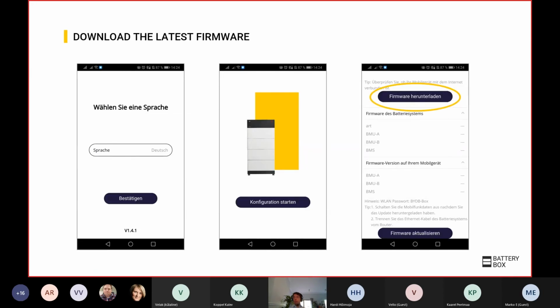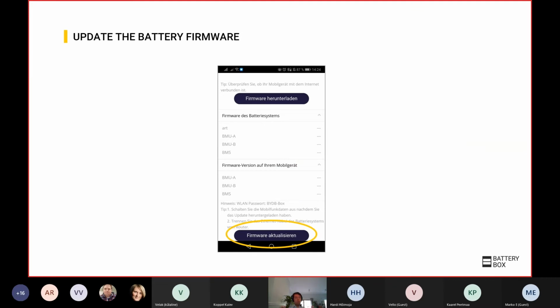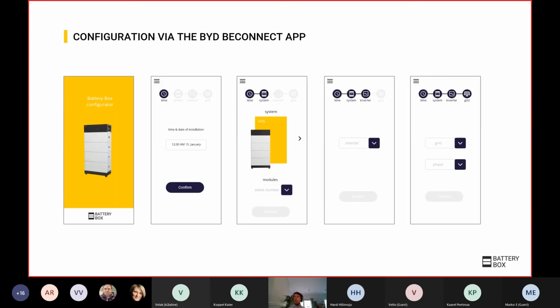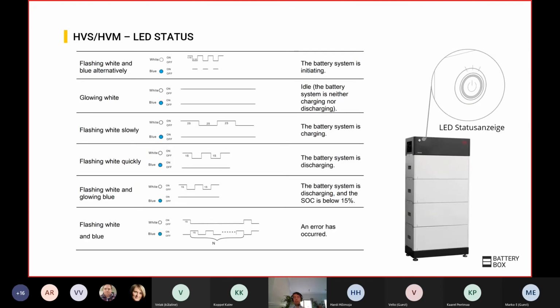When you're using the app to do the commissioning, the first thing it will require you to do is update the firmware. In order to make sure that you have the latest firmware, update the app before going to site, and download the latest firmware before going to site. And once you're on site, just connect to the battery Wi-Fi and update the firmware. The commissioning part itself is very simple. You just need to confirm the time, select the type of battery that it is, select the inverter that it is, and finally select if it's single phase, 3-phase, or on-grid, off-grid. And once that is finished, you will see the LED light in the front of the battery go white. This means that the commissioning has been finished and the battery is ready to connect to the inverter.